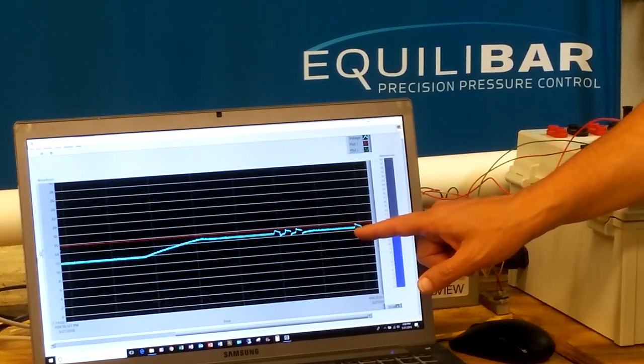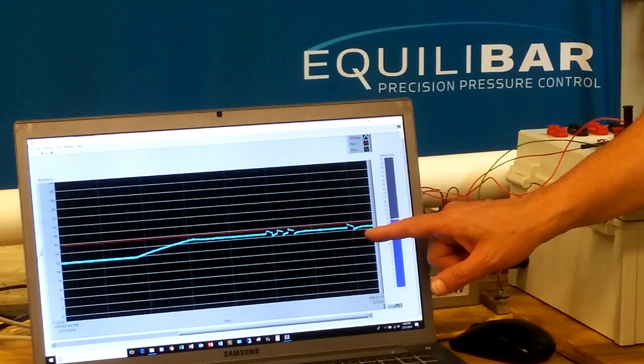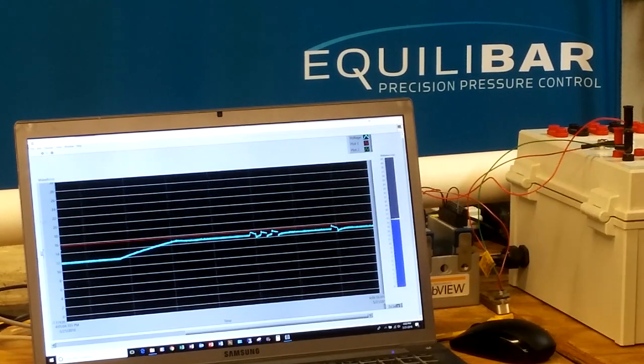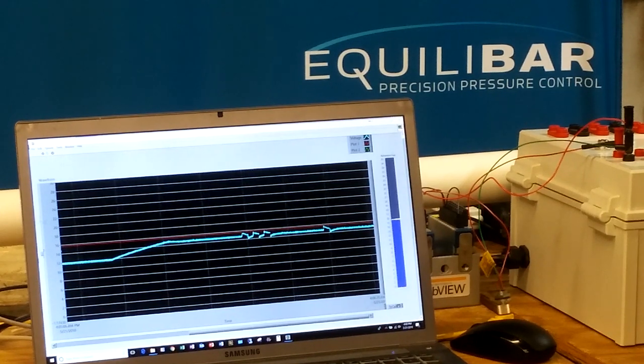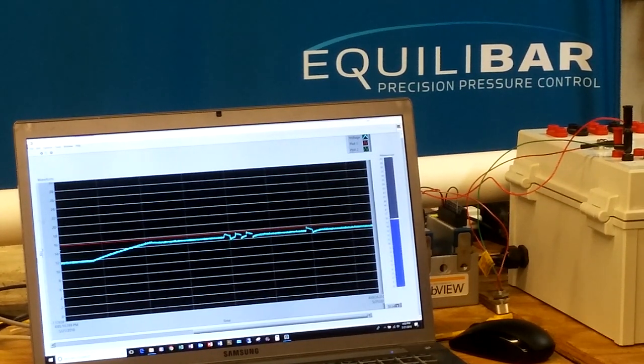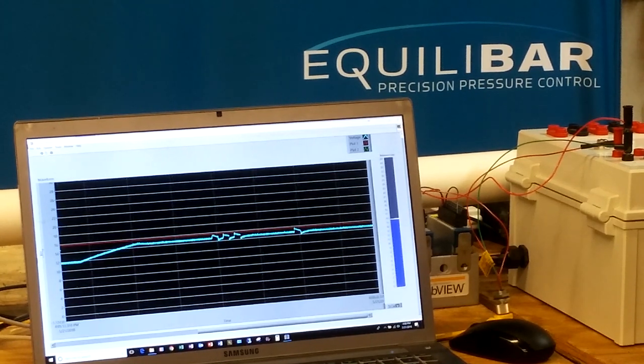So full flow, the same flow that we had before, the same flow disturbance, but the amount of vacuum change in the system is dramatically reduced. That's because of the Equilibar's high-speed ability to respond to changes in flow in the system.